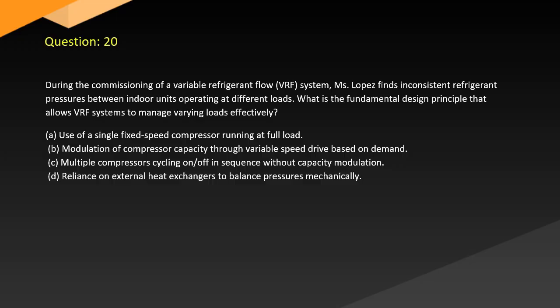Question 20. During the commissioning of a variable refrigerant flow (VRF) system, Lopez finds inconsistent refrigerant pressures between indoor units operating at different loads. What is the fundamental design principle that allows VRF systems to manage varying loads effectively? A. Use of a single fixed speed compressor running at full load. B. Modulation of compressor capacity through variable speed drive based on demand. C. Multiple compressors cycling on-off in sequence without capacity modulation. D. Reliance on external heat exchangers to balance pressures mechanically.